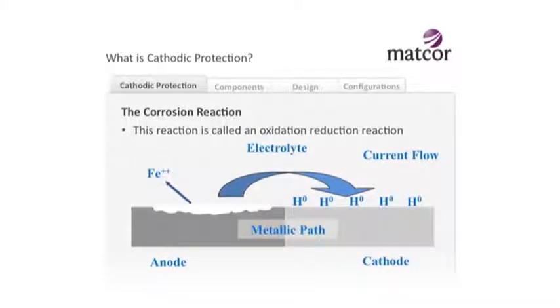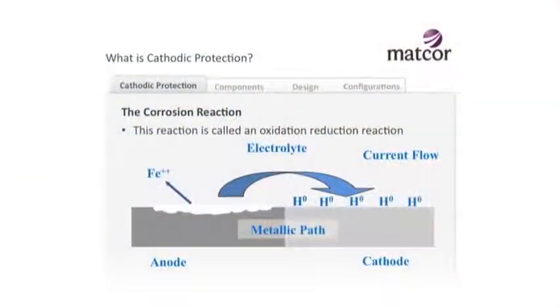So how does it work? The corrosion reaction is what we call an oxidation reduction reaction - a chemical reaction where the metal reacts with the environment to reduce it to an oxide form. At a micro level, one section of a structure is what we call anodic, slightly more negative electrically than the next section. Current flows from that anodic section to the more positive cathodic area, and corrosion occurs where that current leaves the structure. We call this a corrosion cell or a galvanic corrosion cell.